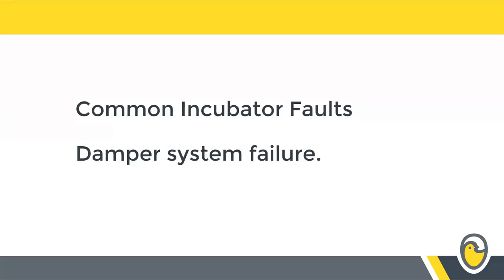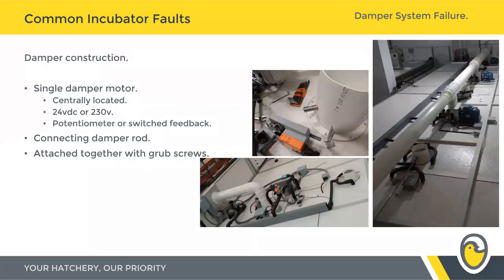We're going to spend the next couple of minutes looking at damper system failures. It's worth going into the construction of the damper system and ventilation system on an individual incubator first. On the vast majority of our incubators, all the dampers on the machine are controlled by one single damper motor centrally located. That motor is going to be either 24 volts or 230 volts. All our recent incubators for the last eight to nine years have all been 24-volt low voltage DC actuators. Older machines, going back around 30 years, have 230-volt high voltage damper motors — so bear that in mind when ordering spares.